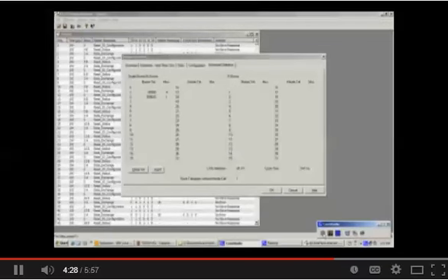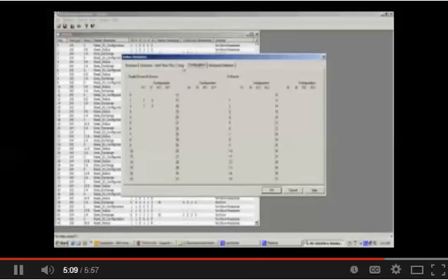Now if I go ahead and add node number 1 to my system, you will see that already I'm starting to track messages to node number 1. The missed packet count you see here is because I was jiggling it as I put it on, so it wasn't making contact until I firmly tighten it down to the flat ASI cable. But I can hit clear all here and have it reset, and you'll see that it tracks correctly. Once again, if I loosen my overall cable connector to my ASI network here, you'll see that I can generate missed packets here to the two particular nodes. And it goes ahead and tracks along and so forth. So this is doing the online statistics of my network.